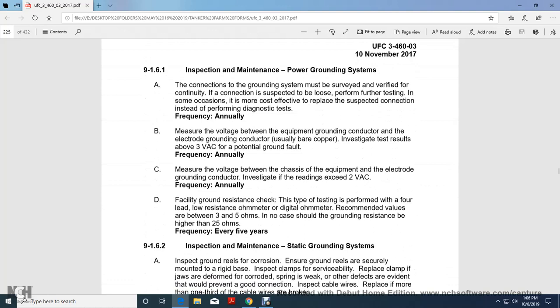The connections for the grounding system must be surveyed and verified for continuity, with suspect connections further tested. In some cases it is most cost-effective to replace the suspected connection instead of performing diagnostic tests. Annually measure the voltage between the equipment ground conductor and the grounding electrode conductor, usually bare copper. Investigate test results above 3 volts AC as a potential ground fault. Measure voltage between the chassis of equipment and the grounding electrode conductor. Investigate readings that exceed 2 volts AC.